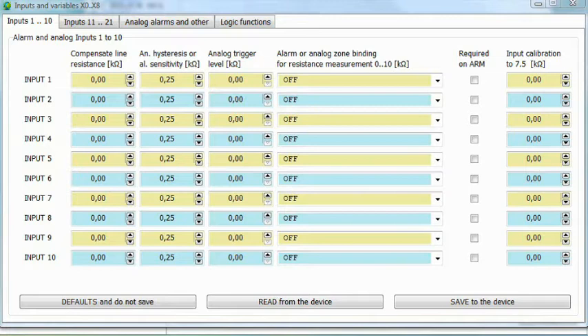On the right you have the input calibration field. Calibration should be done before you connect any sensor to the inputs. Take the 7,500 resistor that you received with the device, connect it to the input and check whether the resistance really is 7,500 ohms. Then calibrate the input by the difference between 7,500 and the real value. You can check the resistance value in the second screen on the display in the middle of the main window.